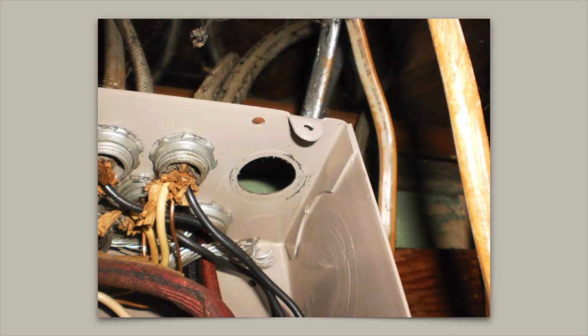The rust on the screws and connections will cause microarcing with the wires in the circuits. This will lead to premature breakdown of the breakers, which will lead to breaker failure, which will lead to a house fire. Anytime rust is noted in the panel, it is a safety hazard and should be written up as a safety defect. Missing covers or knockouts.